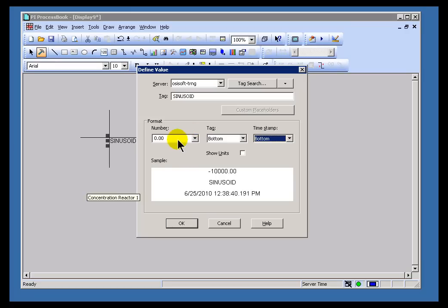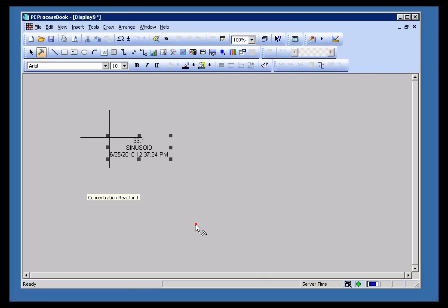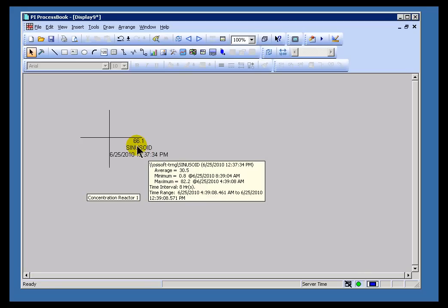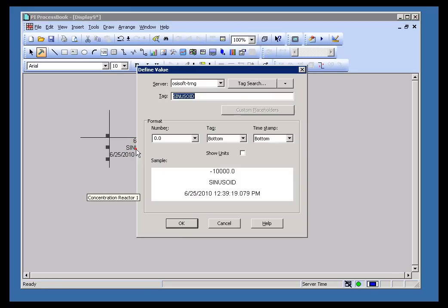I'm going to specify this as one decimal place. Now, I would strongly recommend you carefully consider your decimal places. And there we go, the one decimal place here. Nothing destroys the credibility of a system like PI quicker than when somebody shows, maybe it's a level transmitter that's at one one-thousandth of an inch accuracy. So consider carefully what you choose for your numbering format here.